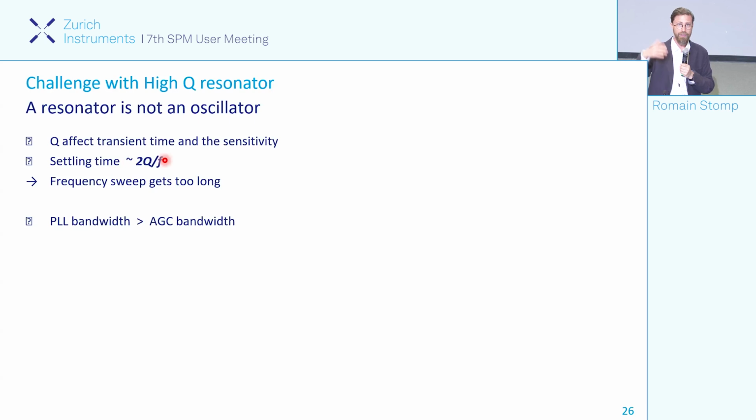So basically, everything that I've shown you, if you want to do this point by point, it will take you a very long time, because unless you know exactly what it's going to be, you need to make a lot of sweeps to get a lot of points, because your bandwidth is sometimes even millihertz. That's why there is a different way.